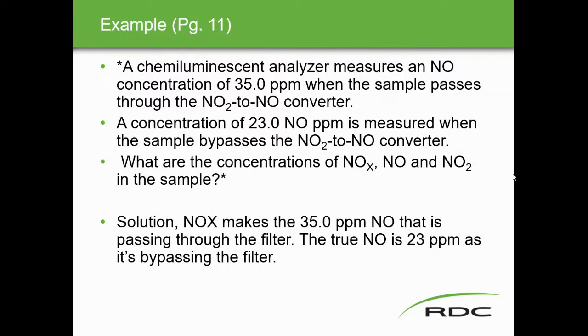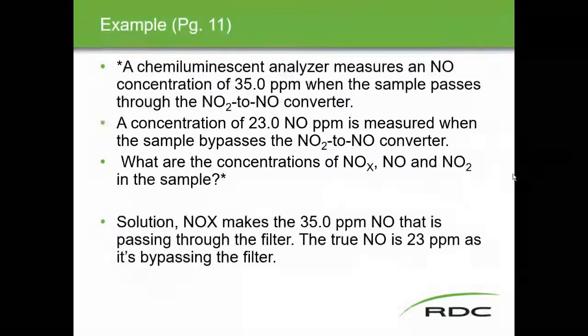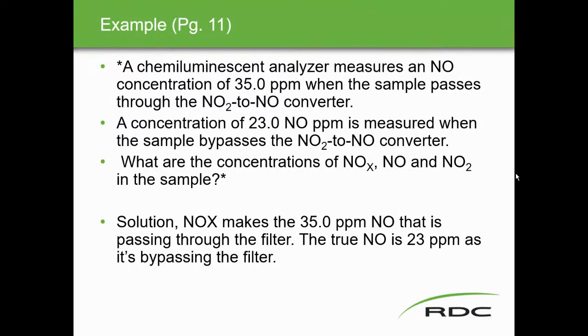Here's a worked example: a chemiluminescent analyzer measures an NO concentration of 35 ppm when the sample passes through the NO2-to-NO converter (NOx mode), and 23 ppm NO when the sample bypasses the converter (NO mode). Therefore: NOx (35 ppm) minus NO (23 ppm) equals NO2 (12 ppm). This is just a simple subtraction equation, shown on page 11 of the notes.